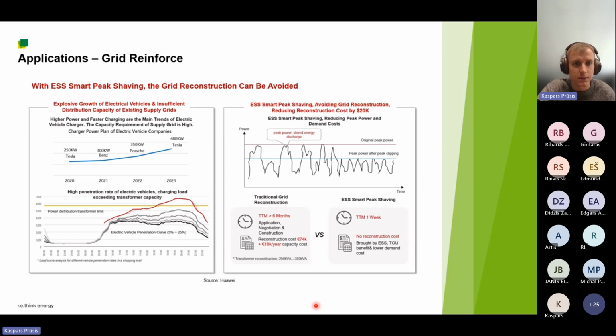Another application that is also relevant, and I believe that it will be more relevant for our countries, is grid reinforcement. By this, we mean that an example would be EV chargers. So if we want to add EV chargers anywhere in our distribution grid, we usually will have to ask for reconstruction of this grid, so that we can add these high output power charging stations, which means that there probably needs to be some more powerful distribution transformer, distribution boxes, etc. And that's very expensive if we have to request it from the grid distribution operator.